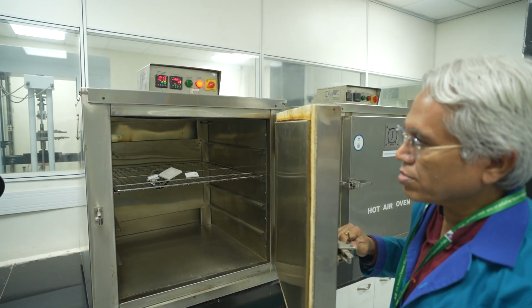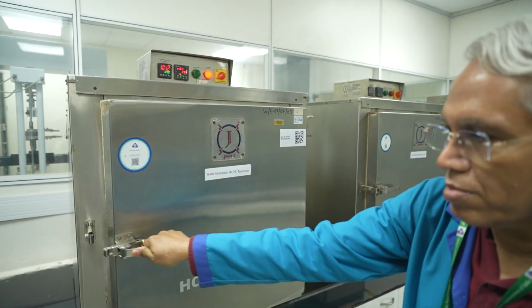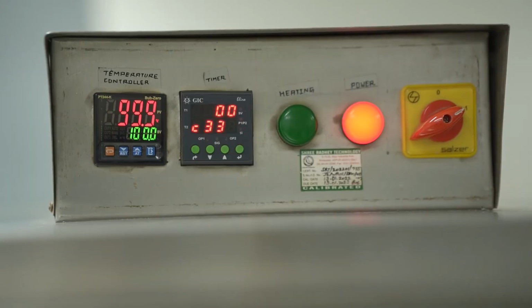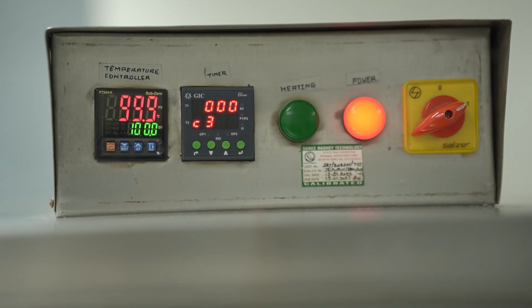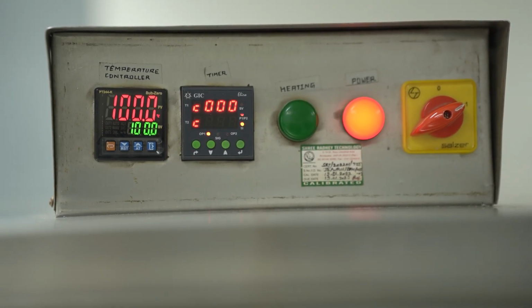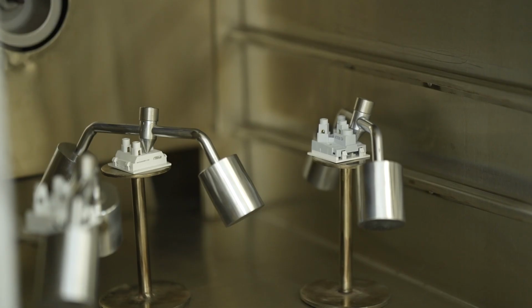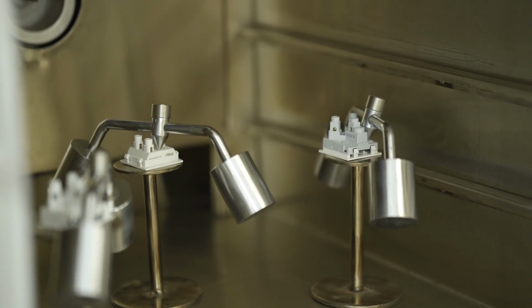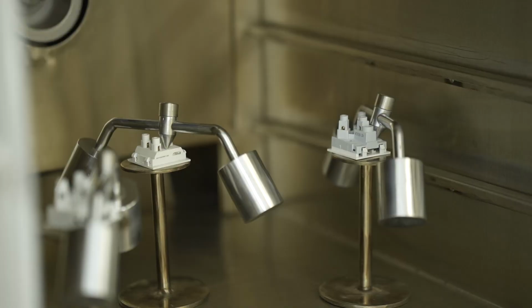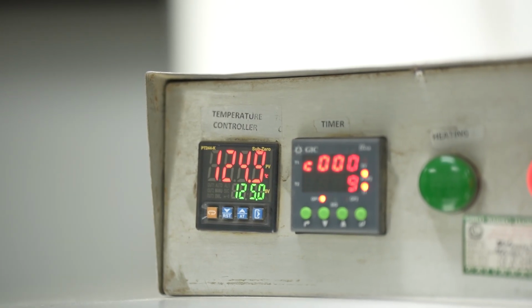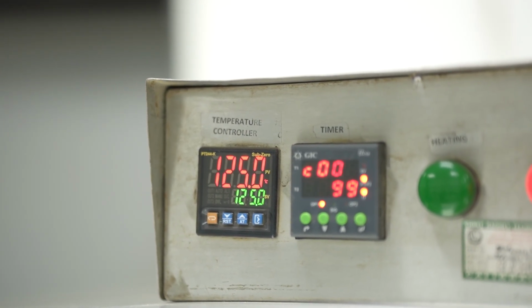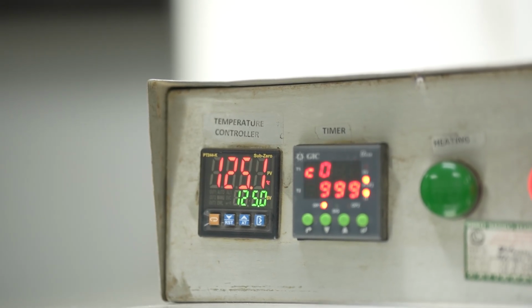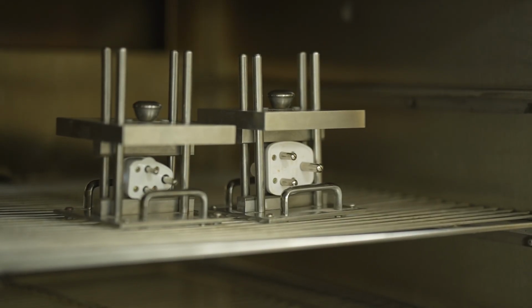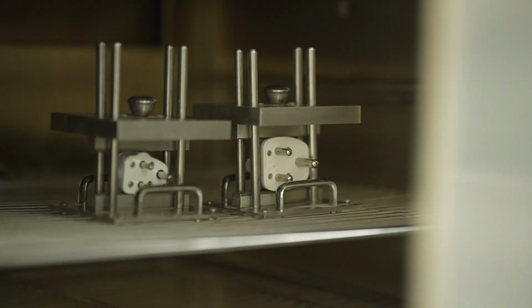Resistance to heat. Clause 25. To ensure the accessories and the mounting boxes are heat resistant, the specimens are conditioned in a heating cabinet for 1 hour at 100 degrees Celsius. After that, a ball pressure test of 20 Newton is carried out at a specified temperature. Subsequently, the impression diameter is measured and should comply with the standard. The plugs are subjected to the compression test of 20 Newton at 80 degrees Celsius for 1 hour.